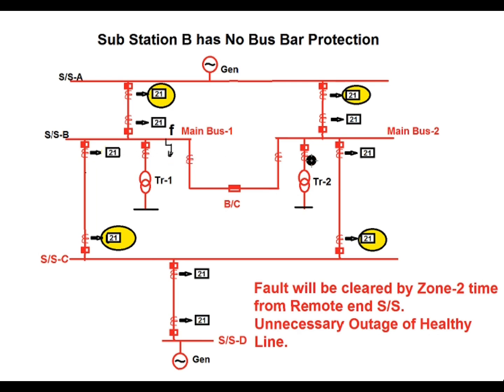So the first disadvantage of absence of bus bar protection is that a fault will be cleared under zone 2 time, which is 350 to 500 milliseconds time delay, and there may be catastrophic damage to the bus under heavy fault current. Again, there is unnecessary outage of healthy lines in the absence of bus bar protection.